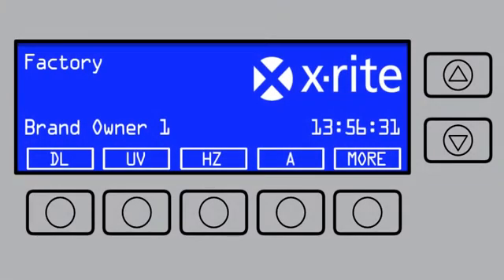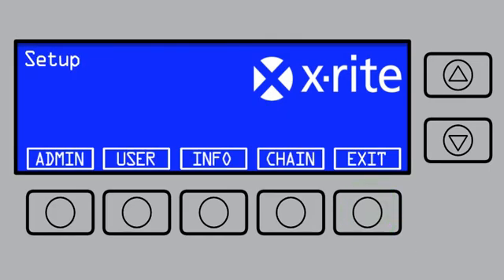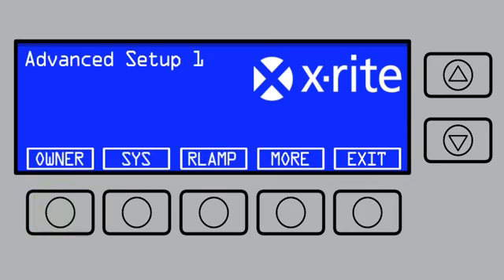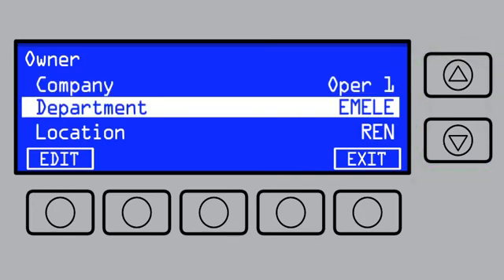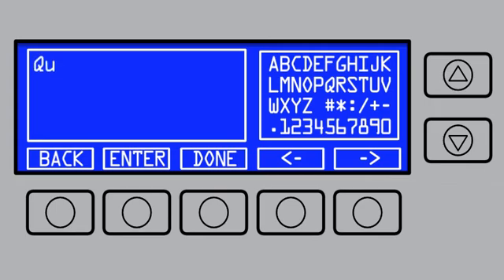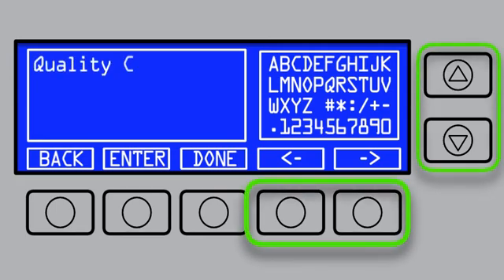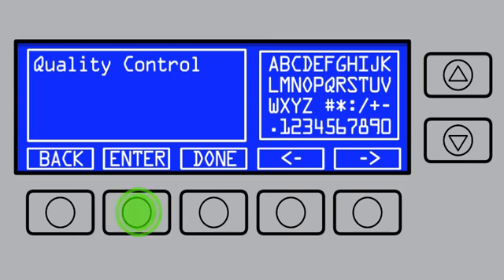From the main menu, press and hold the More button until you see Setup. Press Admin to access the Advanced Setup 1 screen. Use the up and down arrows to highlight the option, then press Edit to enter the editing screen. Press the left, right, up and down arrows to highlight the letters and numbers. Press Enter to add a character. If you choose the wrong one, click back to erase it and try again. You are allowed up to 15 characters.